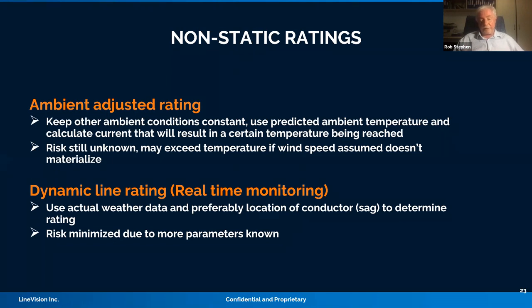Your risk is minimized here because now you're measuring wind speed, wind direction, solar radiation and ambient temperature, and you're calculating the actual conductor temperature for a particular current, knowing all of those parameters. The important thing to know with any of the ratings is your sag to temperature relationship of the conductor. When they install these particular devices, they will do a calibration to make sure that your sag temperature relationship is known. And you can't use the sag temperature relationship from the manufacturers because your conductor would have aged and had different loadings over time.